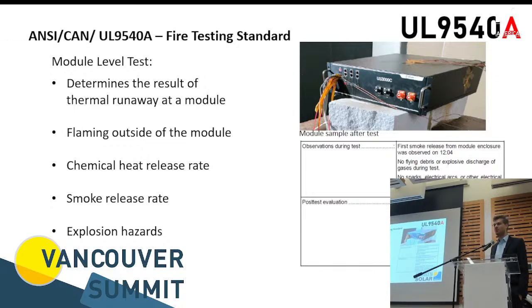What happens to the thermal runaway if one cell, so you start heating one cell and see what happens to all the other cells in that cabinet. And by designing the cabinet in a certain way, the manufacturer of that battery module can contain the problem into that single module, and the risk is not spreading to other modules in that stack. So you're just limiting your exposure of risk.